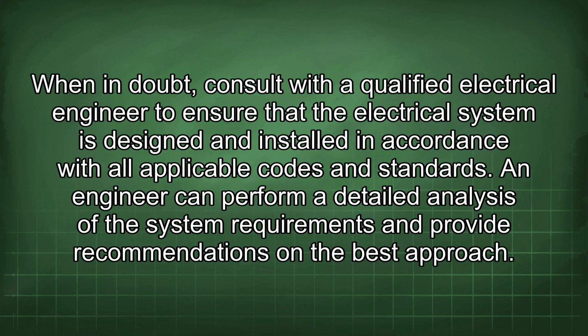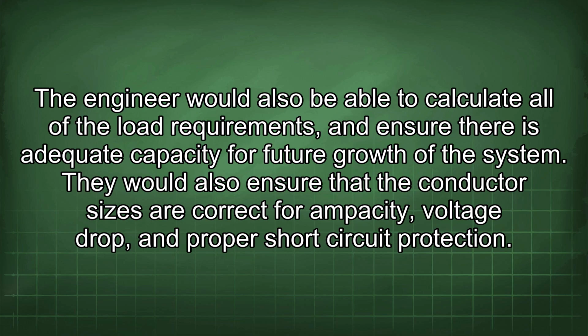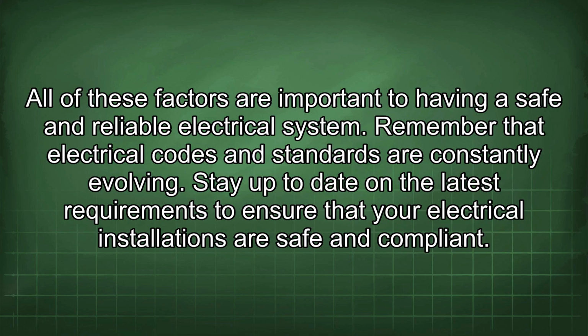An engineer can perform a detailed analysis of the system requirements and provide recommendations on the best approach. The engineer would also be able to calculate all of the load requirements and ensure there is adequate capacity for future growth of the system. They would also ensure that the conductor sizes are correct for ampacity, voltage drop, and proper short-circuit protection. All of these factors are important to having a safe and reliable electrical system.